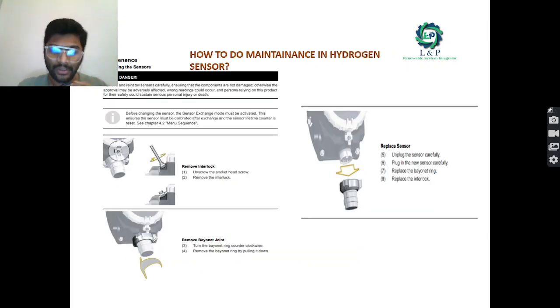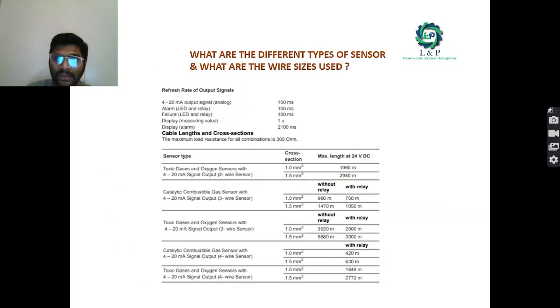So as we did earlier, we know how to install it. If you want to do maintenance, the first and foremost thing is that you need to remove the interlocks. Unscrew the socket head screws and remove the interlock, then remove the bayonet joint. Turn the bayonet ring counterclockwise and pull it down to remove it. If you want to replace the sensor, unplug it carefully, plug in the new sensor carefully, and replace the bayonet ring, most importantly.